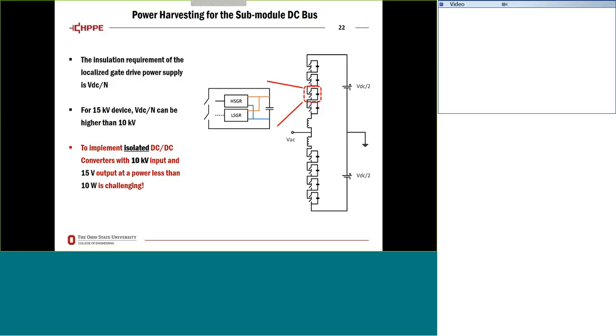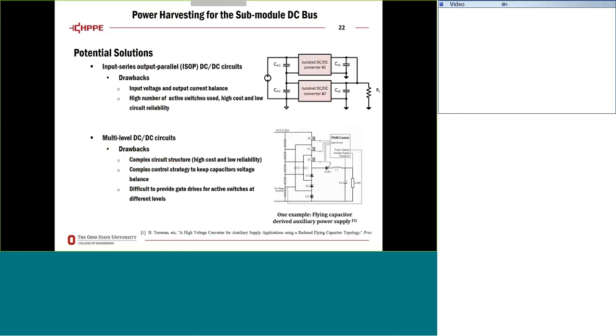At a power less than 10 watts, and that's something extremely challenging. In traditional solutions, people do have circuits to take power from submodules, and that's been done for many years, but not at this voltage level. For current MMC implementations with silicon devices, the DC bus is usually lower than 3 kV, so we are doing things at 3 times higher voltage, and it's not that straightforward.